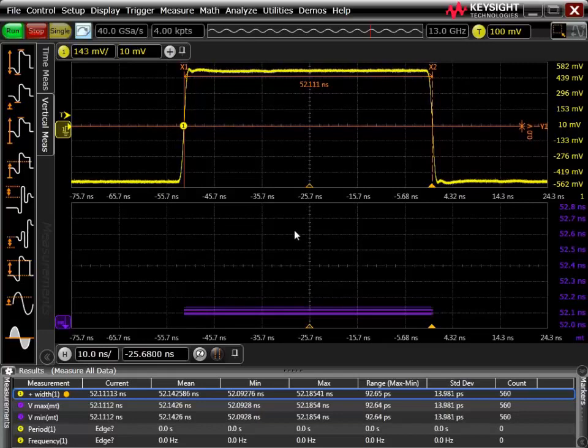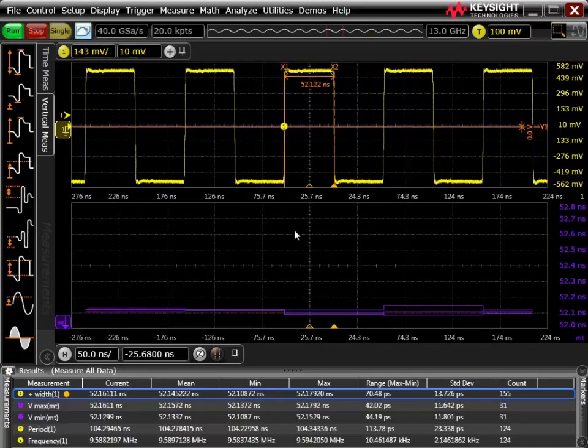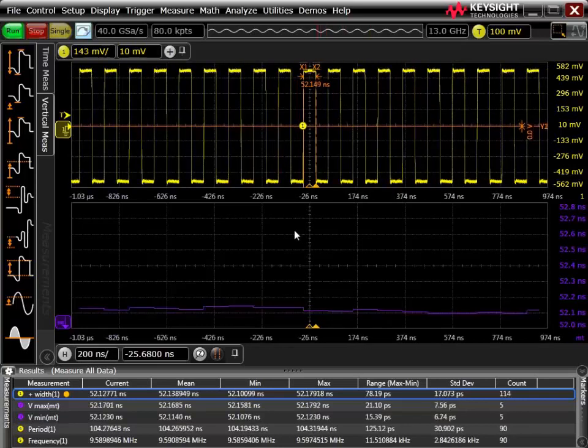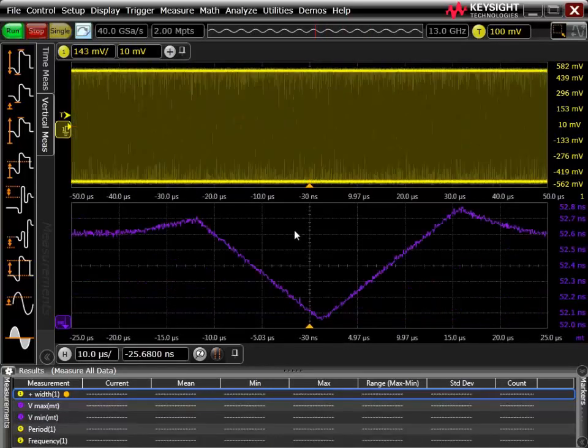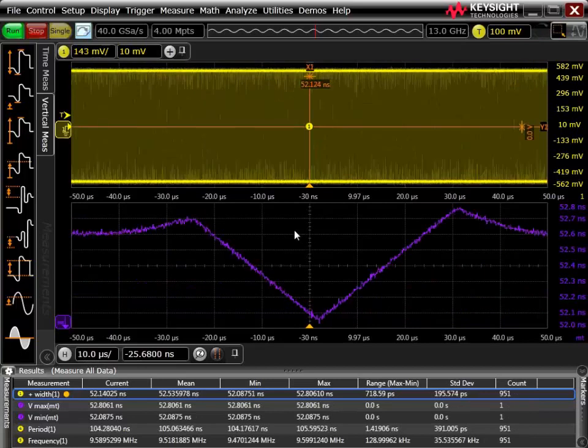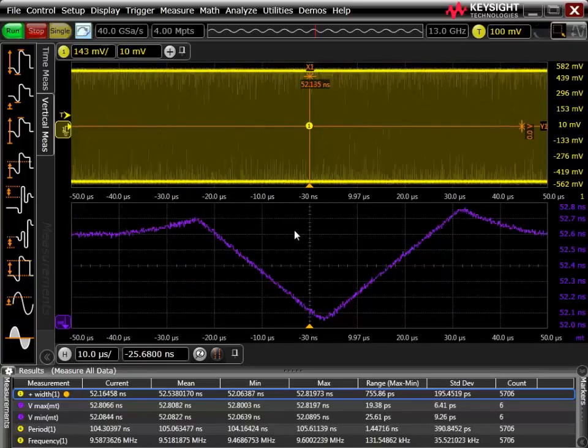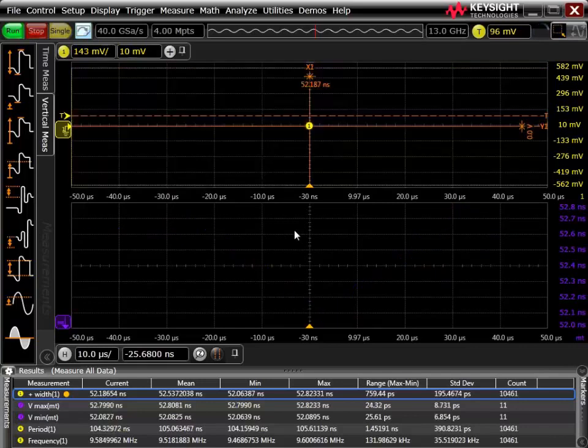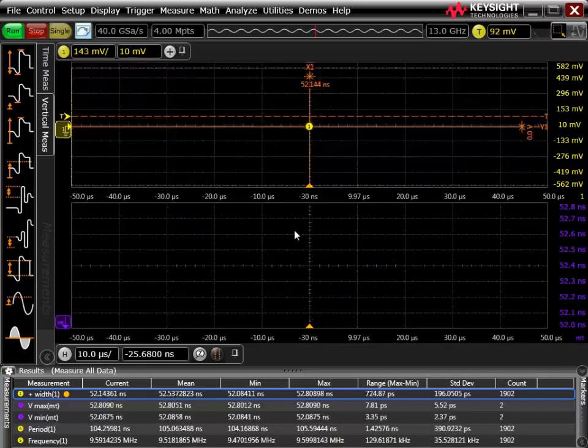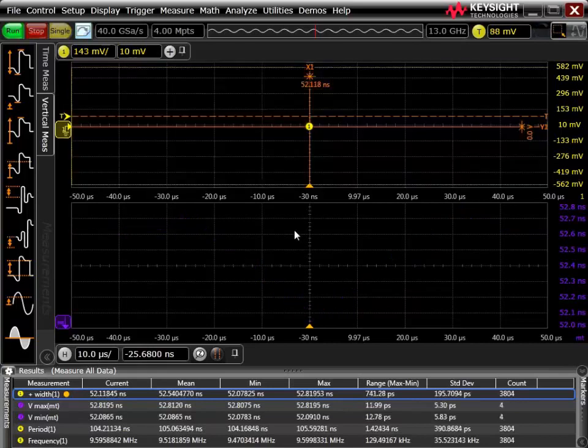Now I'd like to zoom out a little bit and just confirm that we are really capturing the worst-case events. There you can see that negative peak, and we're right around there every time. If I drop my trigger level down just a touch, I'll get closer and closer to that worst-case peak being at center screen.